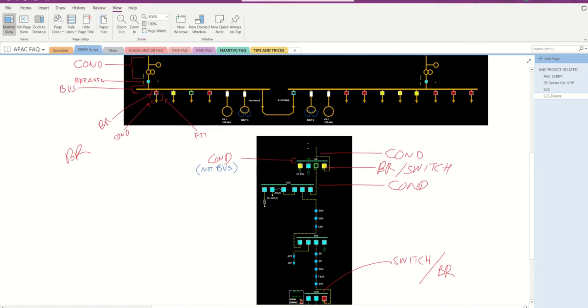On the distribution network, here's the conductor, breaker, conductor. Even this one that works as a bus, we have to assign conductor in here, because after the feeder main of the substation transformer, I mean after the feeder main of the distribution level, you can only put conductor, breaker, or switch. No bus, no feeder main, and no station transformer or substation transformer.